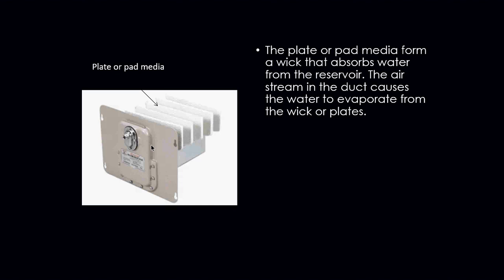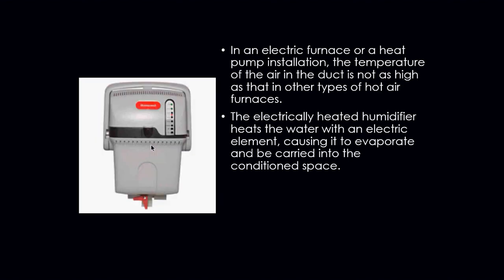Your plate or pad medias form a wick that absorbs water from the reservoir, and the air stream in the ductwork causes the water to evaporate from the wick or the plate. Now you have your more common and more modern, I suppose, types of humidifiers, and these are your electric furnace or heat pump installation type humidifiers. And the temperature of the air in the duct is not as high as it would be in your typical hot air furnaces, but the electrically heated humidifiers heat the water with an electric element, causing it to evaporate and be carried into the conditioned space.